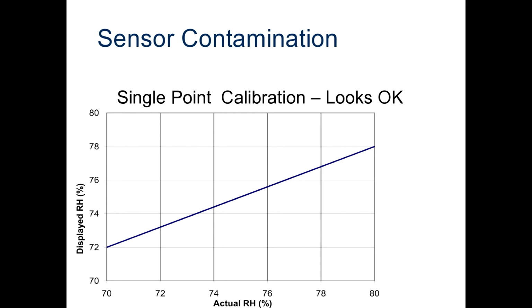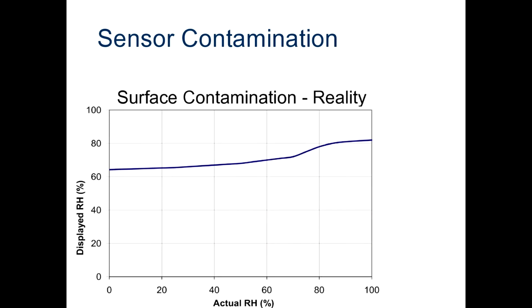So everything looks fine. But if that same sensor were calibrated over a very wide range, we'd see quite a different picture. Again, the actual RH is shown along the bottom with the measured RH along the side. Now, again, it looks great at 75%, but if we were to change to higher humidity or lower humidity, the values are quite inaccurate. And the problem here could be that if the measured system, which may be operating at 75%, goes out of specification, let's say it's a chamber that drops to 70% or 80%, we may not get an alarm because the true change in humidity is not being measured.